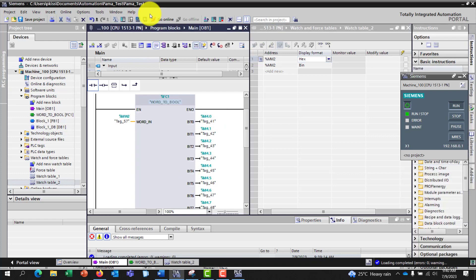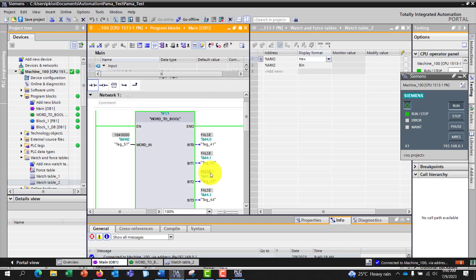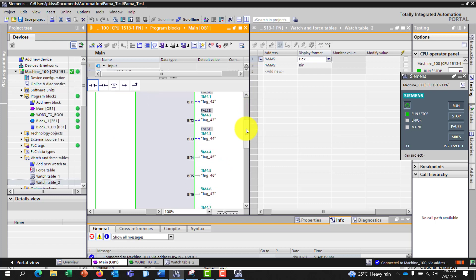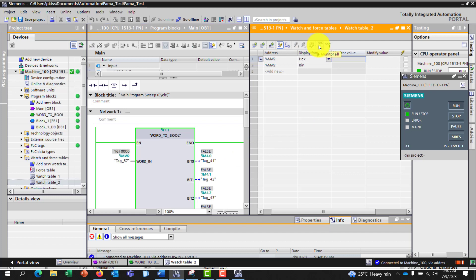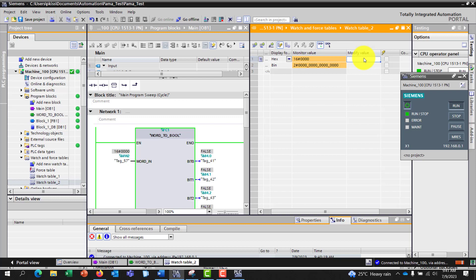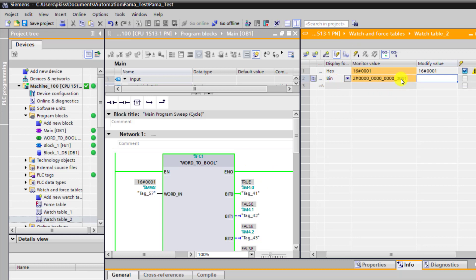I click go online, then put on the monitor view. We can see our data and bits all indicating zero. I go online on the FC view as well. I can now send a value — I'll send one — and we can see which bits come on. I write it and we can see bit zero becomes true. We can see the word in binary as well. Then I change it to 2 and write it.